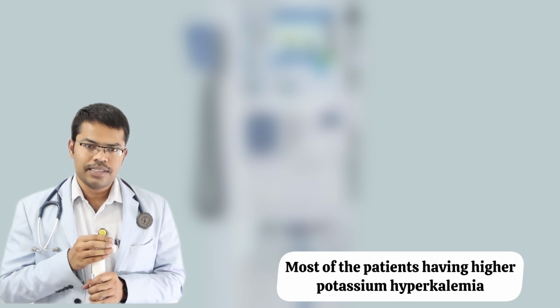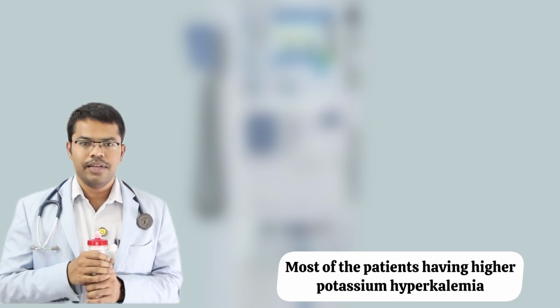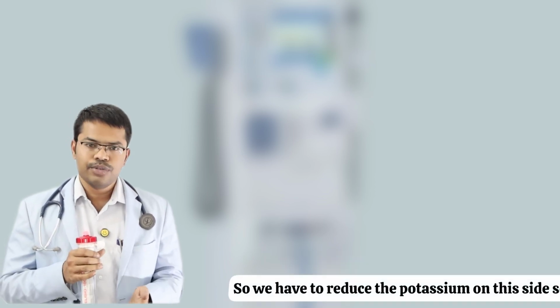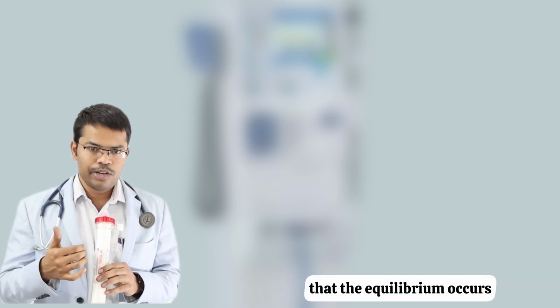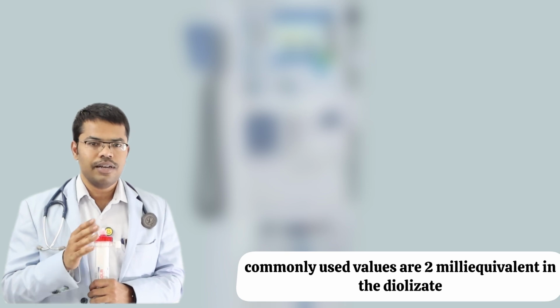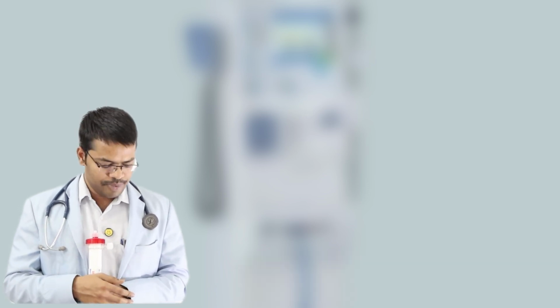Most of the patients have higher potassium, hyperkalemia. So we have to reduce the potassium on this side so that the equilibrium occurs. The commonly used value is 2 milliequivalent in the dialysate.